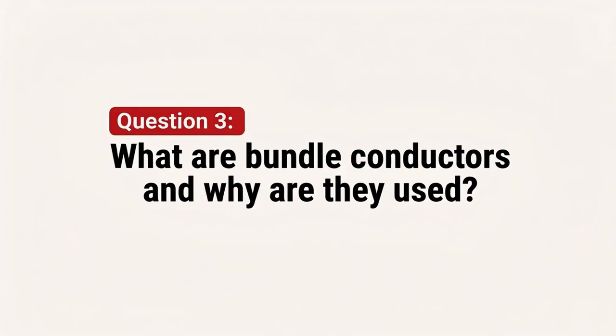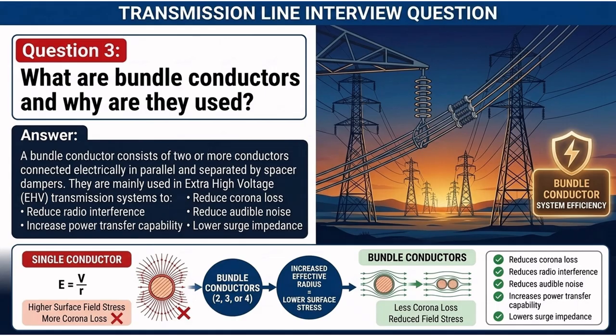What are bundle conductors and why are they used? A bundle conductor consists of two or more conductors connected electrically in parallel and separated by spacer dampers. They are mainly used in extra high voltage (EHV) transmission systems to reduce corona loss, radio interference, and audible noise, increase power transfer capability, and lower surge impedance.